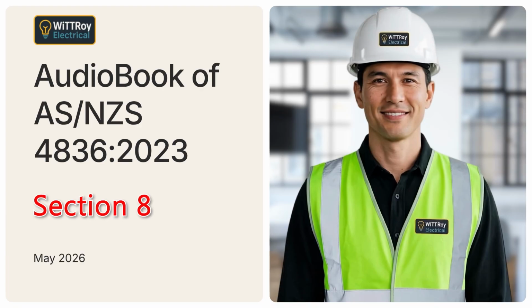Chuck keys tied to portable drills can also create risk if they contact exposed energized conductors or live conductive parts. In practical terms, before drilling, cutting, fixing, or penetrating a wall, floor, ceiling, or structure, think about hidden wiring. Do not rely only on where you think the cable should be. Check, scan, assess, isolate where needed, and control the risk before the tool is used.